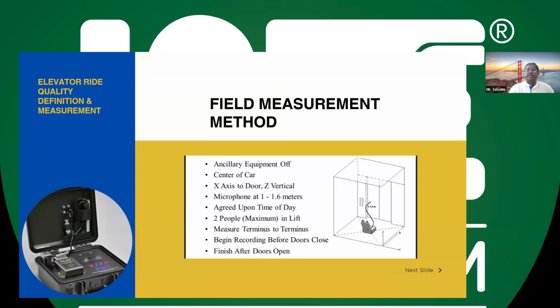And how to make measurement in an elevator? See, the elevator ride quality measurement equipment, the vibration equipment, is kept at the center of the elevator, and it should be pointed towards the door. And you have to have the mic at 1.5 meter distance, and the mic has to be pointed towards the door. This is how you have to place the meter and the mic. And not more than 2 persons are allowed inside the car when you make the measurement. The conditions are: you have to switch off any fan or any voice announcement system. Any external noise making equipment has to be switched off. You have to keep the measuring equipment at the center of the car.